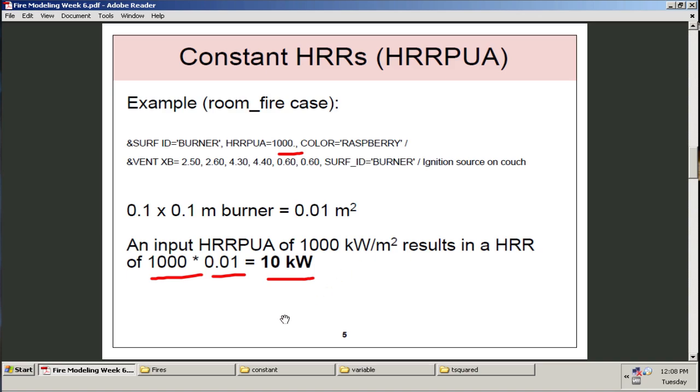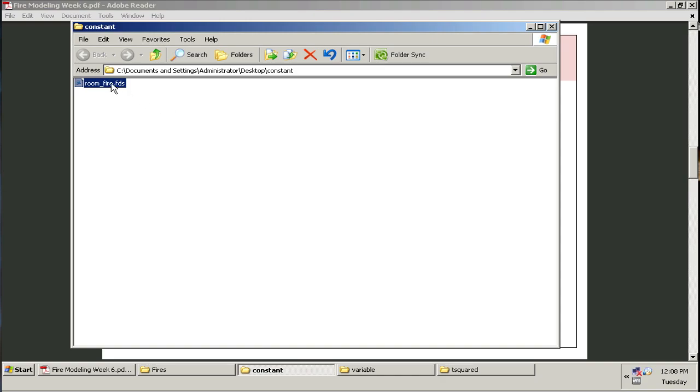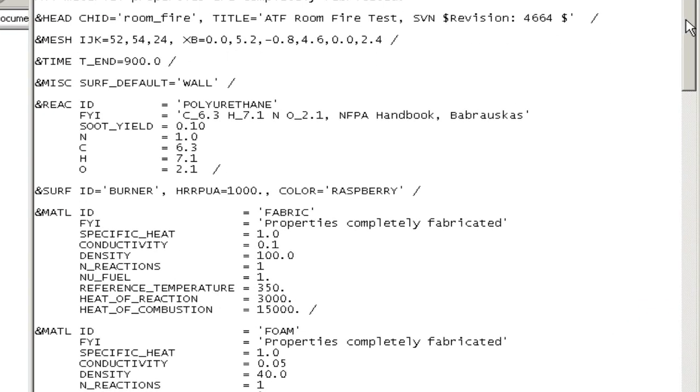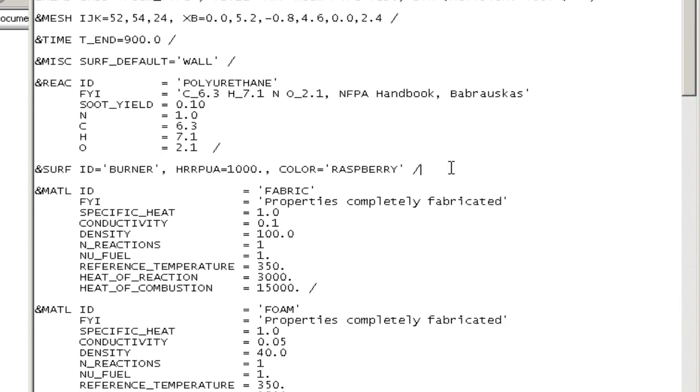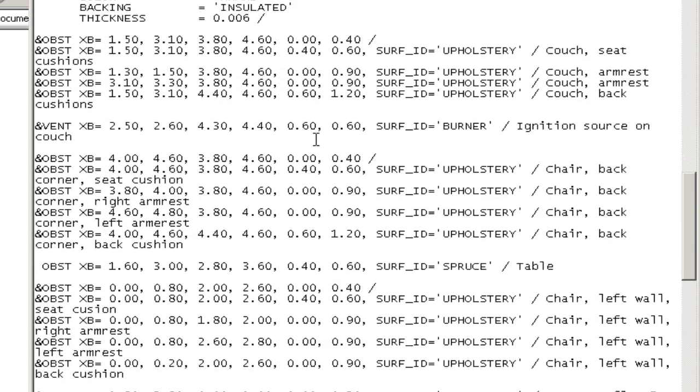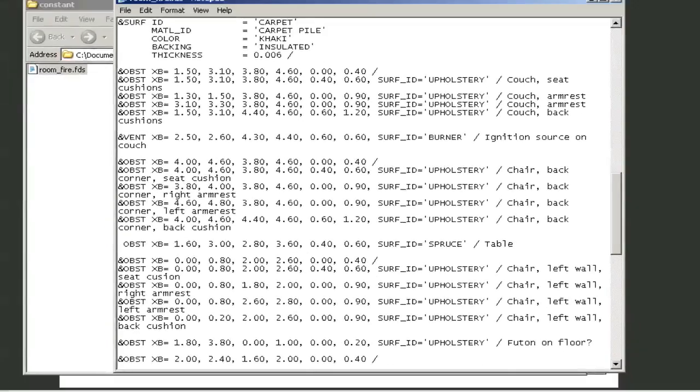In this case, we have 10 kilowatts. I'll go ahead and open that constant folder. If I double click this, I have it set to open in Notepad. If we scroll down, we have the SurfID here. There's that burner line it's talking about. There's the heat release rate per unit area. And if we go down a little bit in the file, we see the vent line here. This is exactly as shown before. It's 0.1 by 0.1 meters. So, the heat release rate coming out of this burner is going to be about 10 kilowatts.